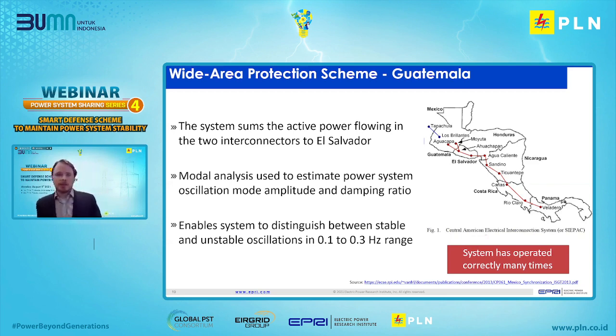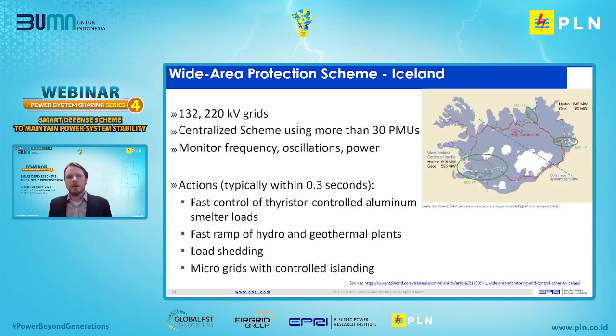Moving on to the next example, and the final example I'll give today, much like the previous one, in Iceland, they have a number of stability issues with the grid. Their grid is primarily based on a ring arrangement, which you can see in the graph in the top right here. Most of the power is provided by hydro and geothermal generators, and they have a number of large aluminium smelting plants. So in this case, if any of the lines in the ring trip, there can be a reversal of power and significant oscillations on the system, which can lead to system collapse.